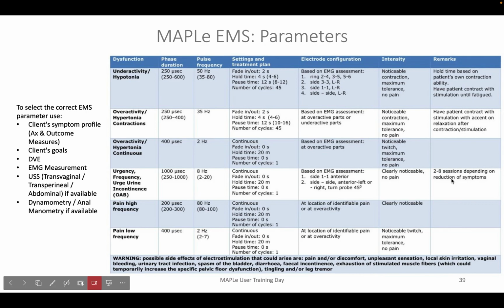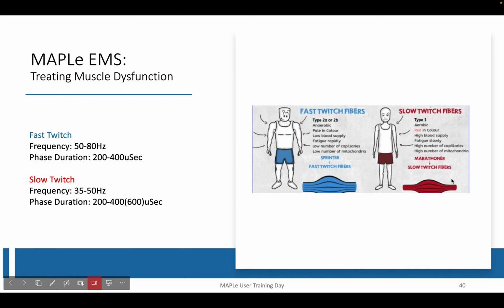Because 50 is the overlapping score, it's very rarely used in electrical stimulation. So we can go through these specific settings, and you can try them out during the Maple Basic Day. Here is a reminder: the fast twitch frequency will be 50 to 80 with a phase duration of 200 to 400 microseconds. And then the slow twitch fibers are more likely to activate between 35 to 50 hertz frequency, and then a phase duration of 200 to 400 or 600 microseconds, depending on the sensation that the patient experiences.